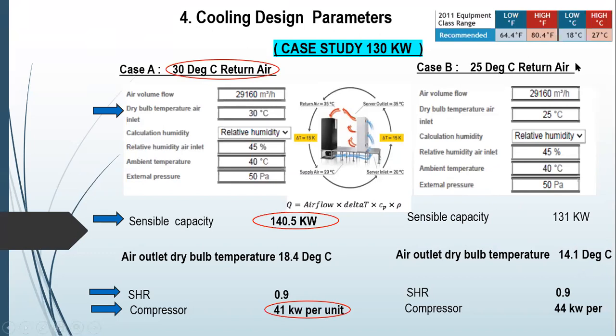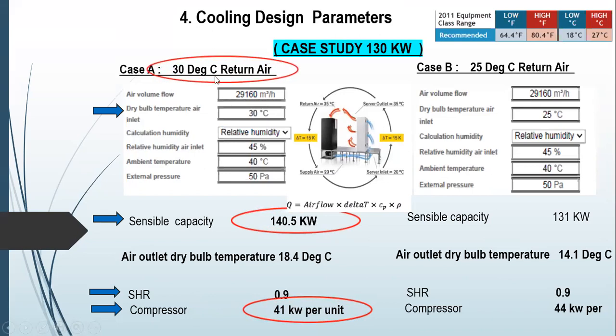But as per ASHRAE norms, the supply is 18 to 27. So this is actually not required. This is overcooling, where the temperatures are very low. If you look at case A, the supply air temperature is taken at 18, which is again low. We could go up to 27, and with a delta T of 10, 11, the return air being 30, the impact is a drop in the power consumption of the compressor as against case B. There is an incremental increase in the cooling capacity, the sensible capacity, with the return air kept at 30. All other parameters are kept constant in terms of the ambient and the ESP.